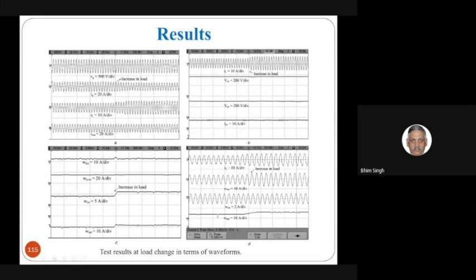We have a grid voltage, a grid current, a load current, and typically an inverter current. There may be a change in the load current relative to the grid. If the load is increased, the load consumes more power, but the generation from solar is constant. That's why the grid power or grid current is increased, as you can clearly see here.